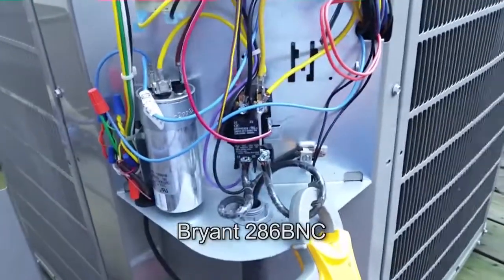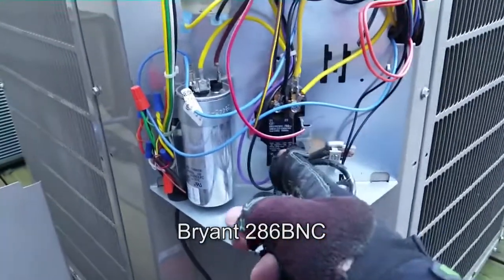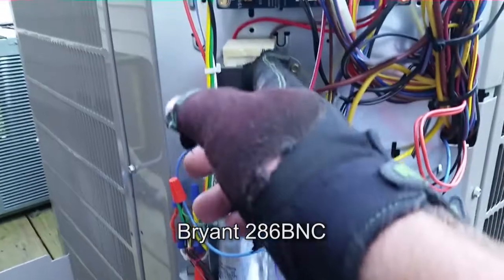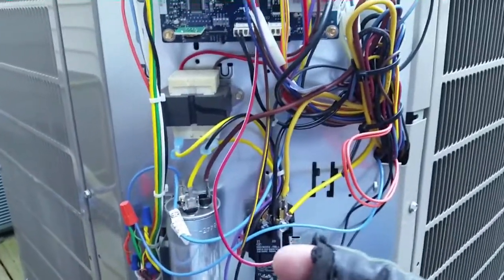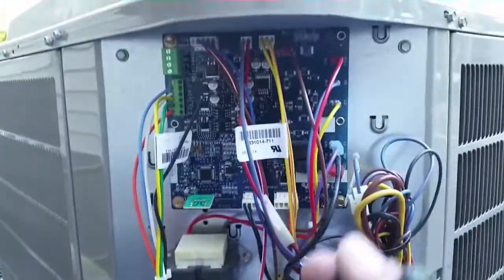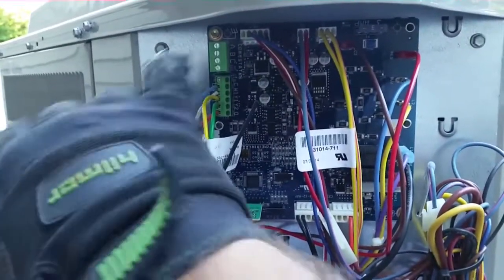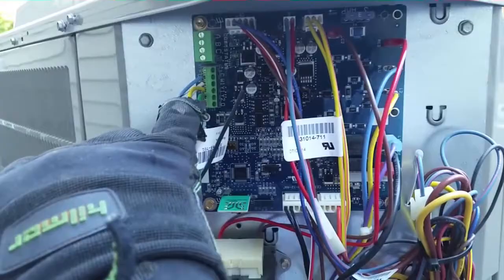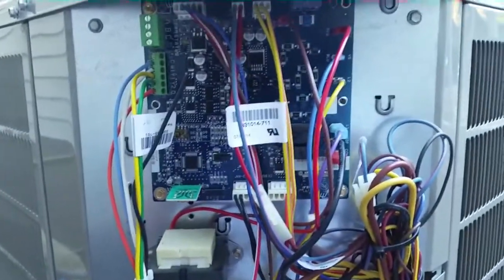Guys, I'm just checking the capacitor here. Dual run capacitor is 37.5. It was fine. It's our contactor, dual run capacitor. Got transformer outside because this can be used as a communicating system as well. There's our board for the outdoor unit. You have our communicating terminals up here, Evolution, whatever, and our regular 24 volts connections there.